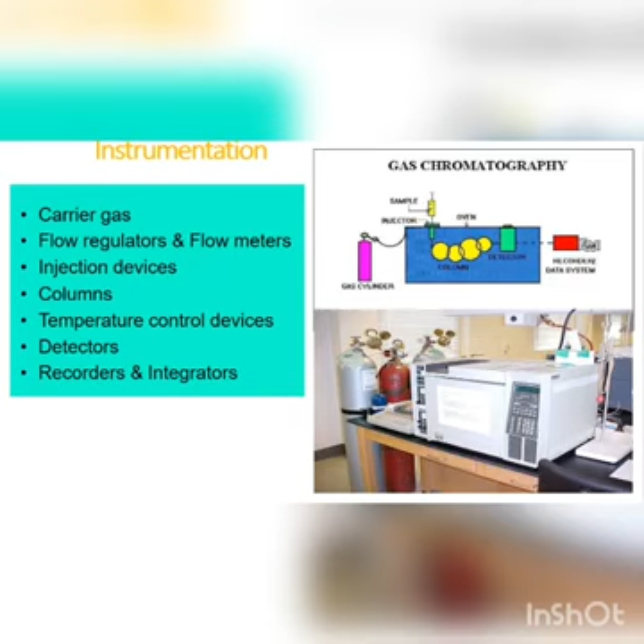The first part is carrier gas. The carrier gas is the mobile phase in GC. What are the requirements of a carrier gas? What should a carrier gas be like? It should be inert, meaning it cannot react with any instrument components. It should be suitable for the detector and other materials used in the instrument. It should be highly pure, easily available, cheap, should not cause a risk of fire, and should give the best column performance.